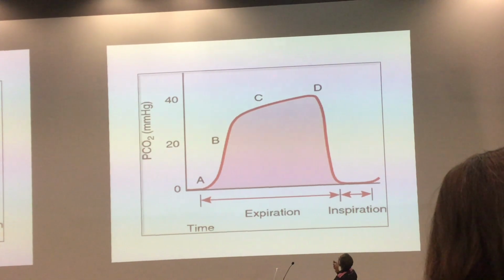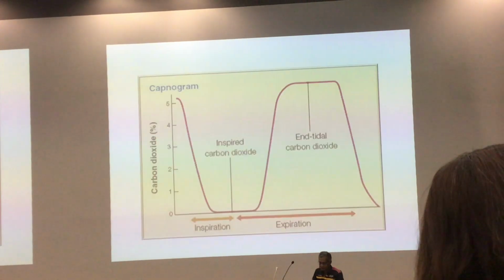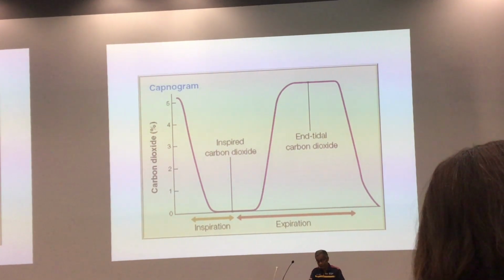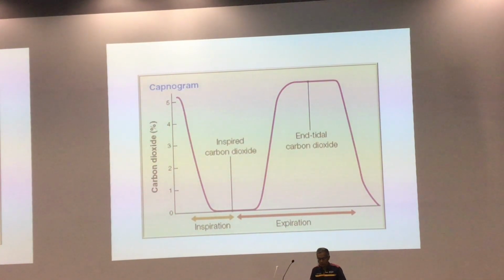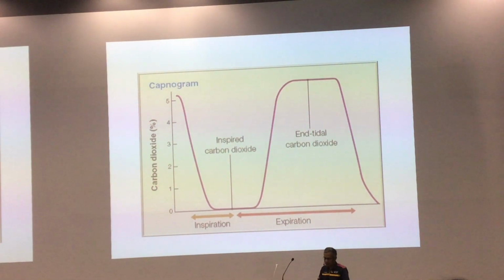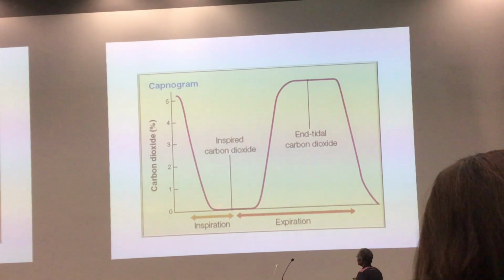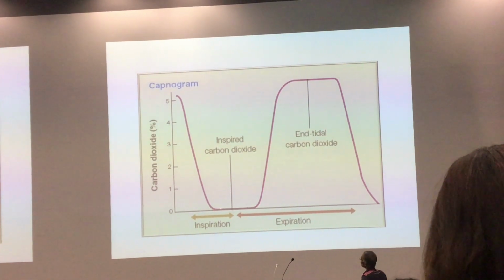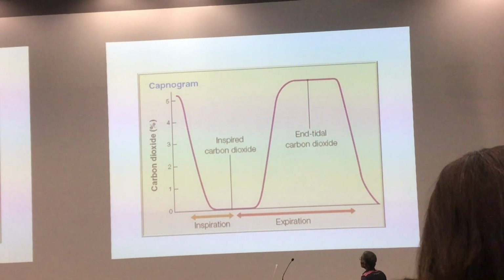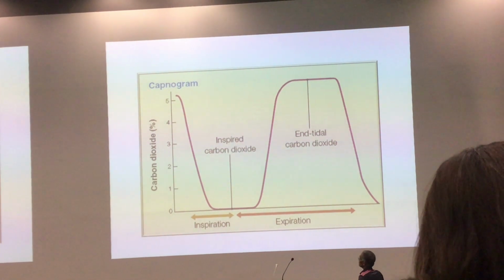So this is what you get. You have A, B, C, D, expiration, inspiration. You should be able to draw this diagram and interpret the phases, right? It is not part 1, this is part 2 now. This is applied clinical measurement. As you see from here, there is 0 CO2 because of inspiration. Let's say you get FiCO2 of 5 millimeters of mercury, which means there is rebreathing in the circuit, right? You have to change the soda lime, right? FiCO2 should be 0. So this is the end-tidal CO2, mean of 40.